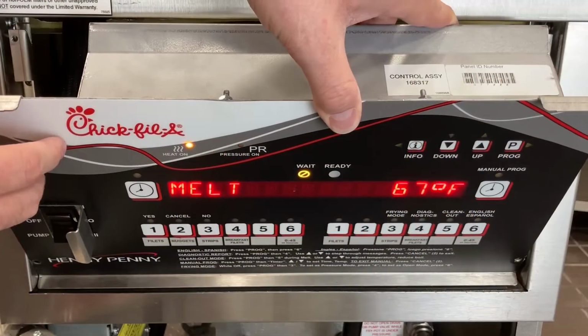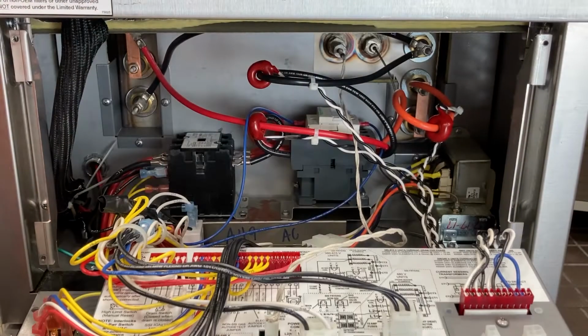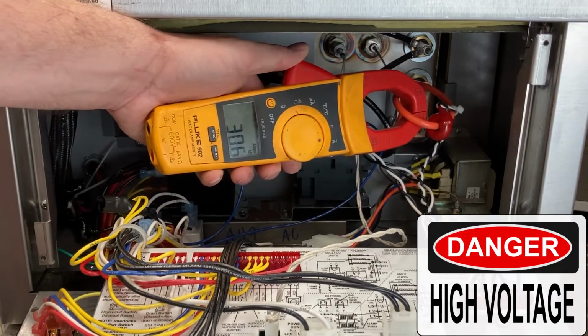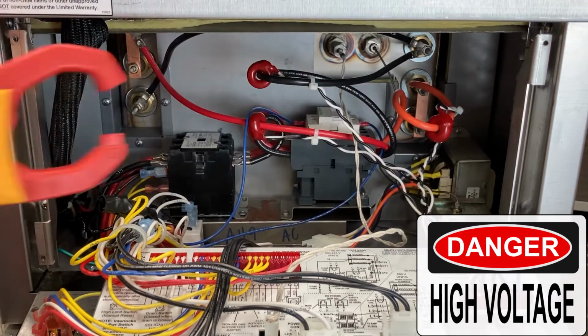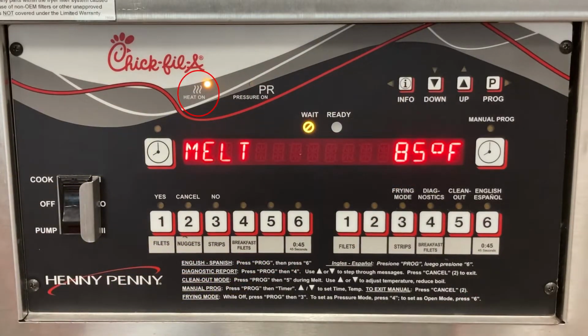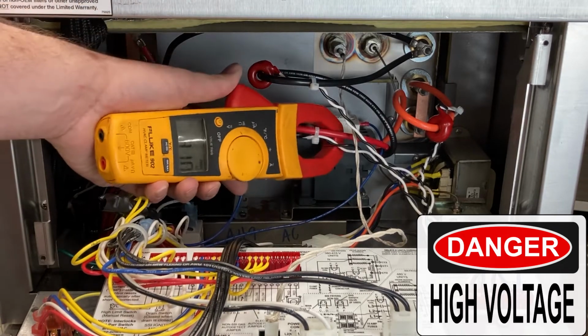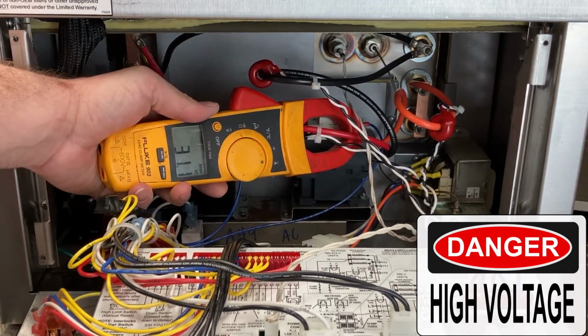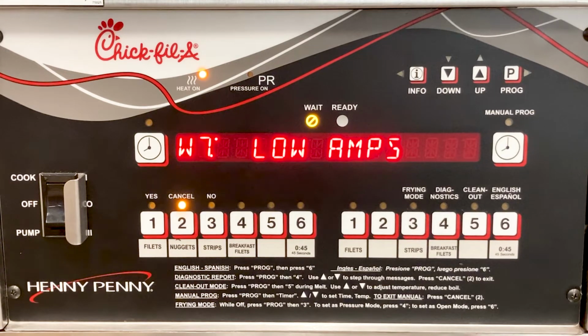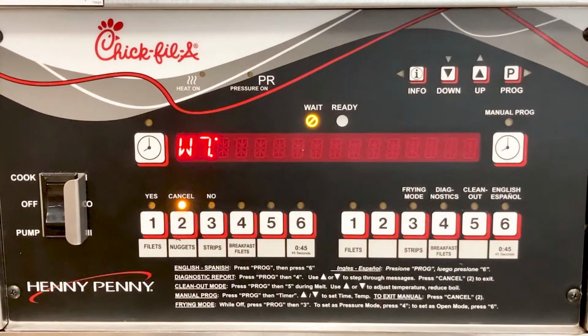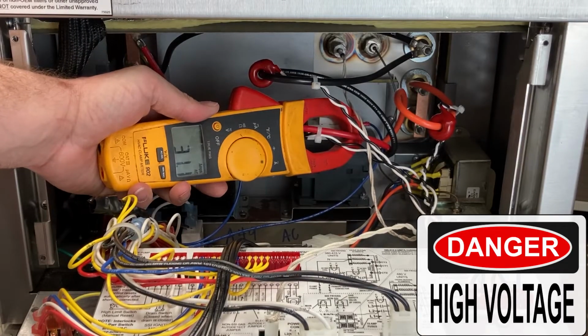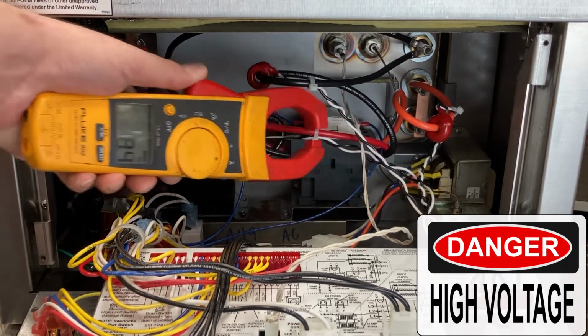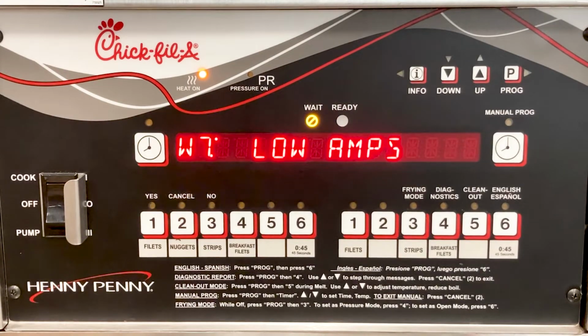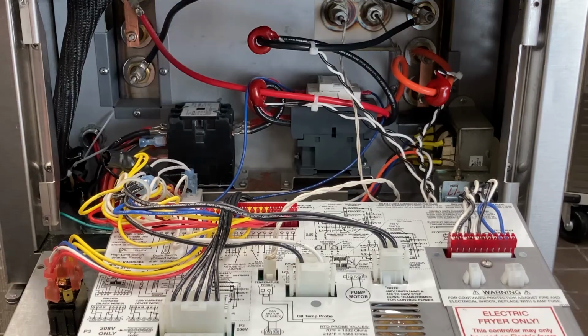If needed, the next step with the control down is to take an amp draw reading on all three wires coming off of the heat contactor going to the heating elements while the unit is heating. All three readings should be very close to each other. Compare your readings to what the amp sensor read on the control. If one of the amp sensor readings on the control is 0 or lower than the other two readings, compare that to the reading that you took. If your reading showed all three legs giving proper amp draw, then we likely have a faulty amp sensor.